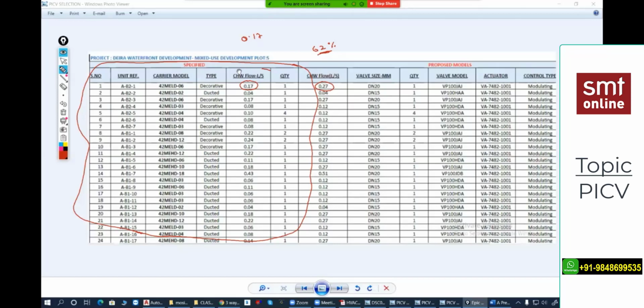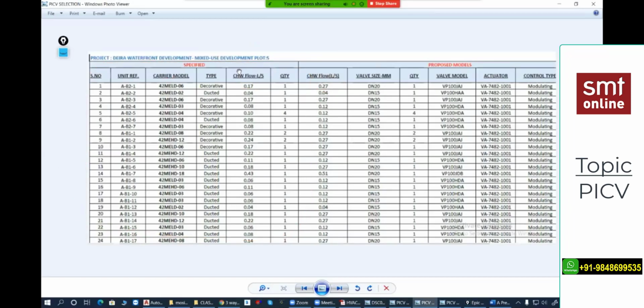I think they've used this: 0.24, 0.27, 0.22, 0.17. And you see, this is actually carrier make. Sorry, this FCU is carrier. This is a different make. So as per availability, if your manufacturer has it, you need not miss it. Exactly, you'll not get it, so that's the reason balancing is required. Balancing is also very simple. Even the installation people can do this after installation. Actually, we used to set before installation so that it will be easy. No problem, you can set before. That is also very easy.